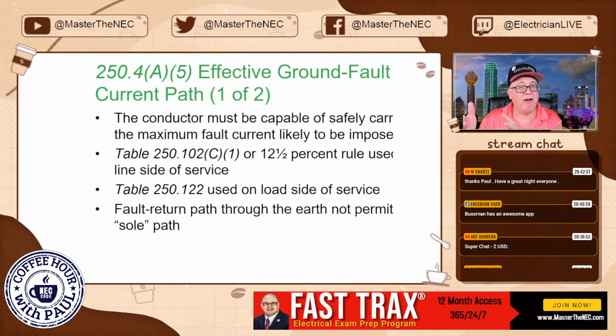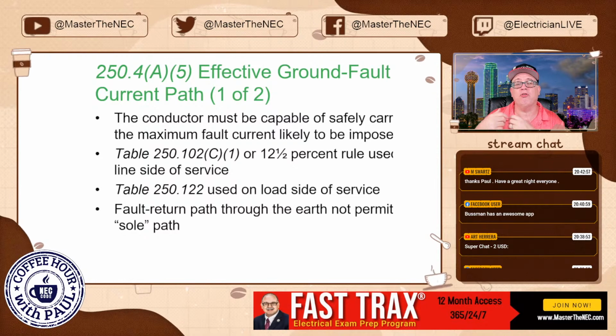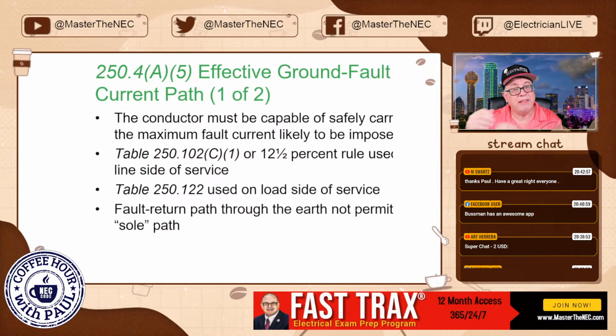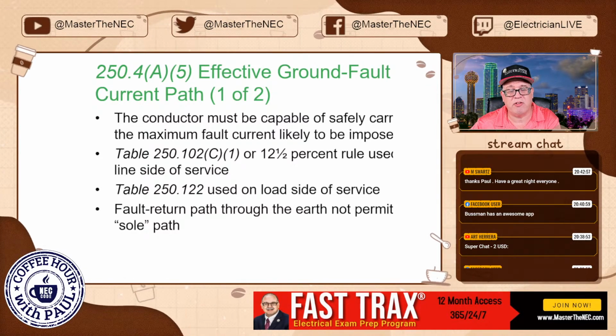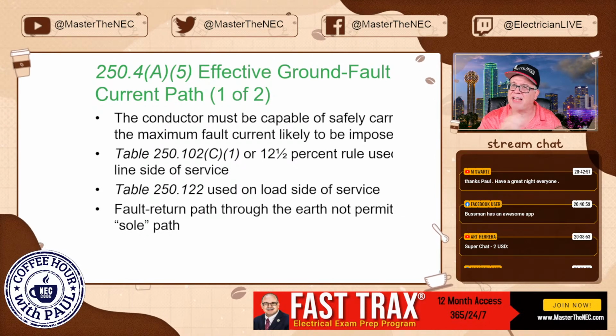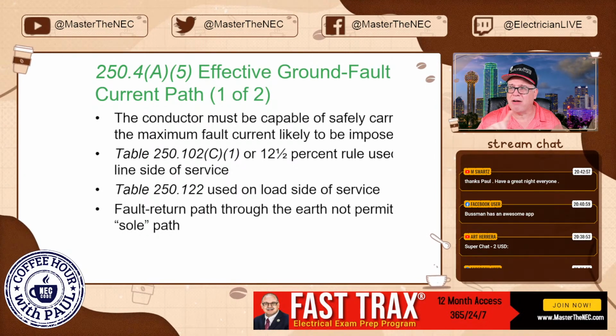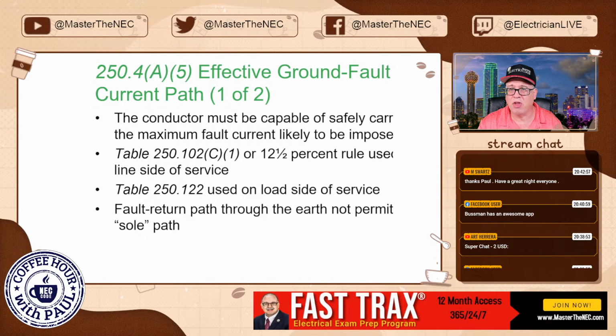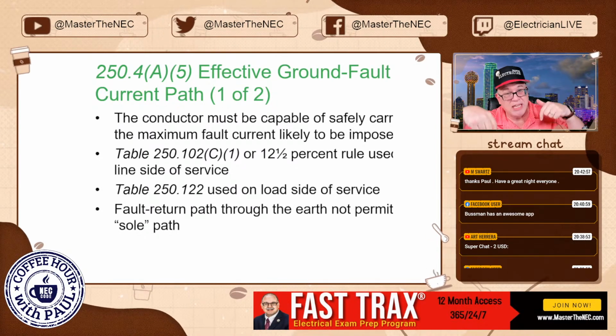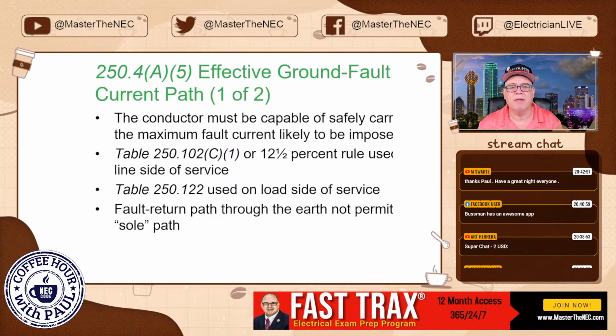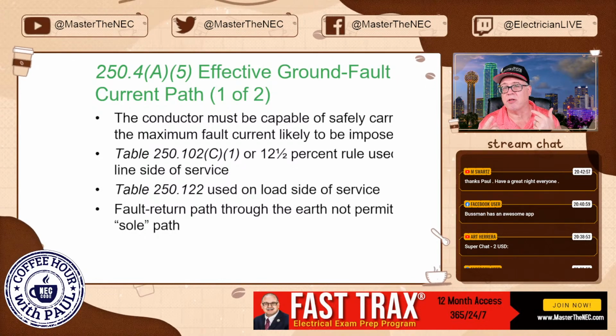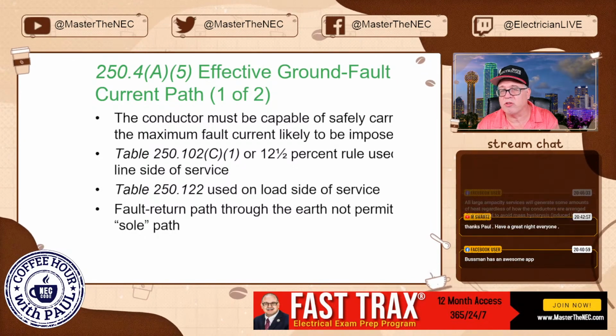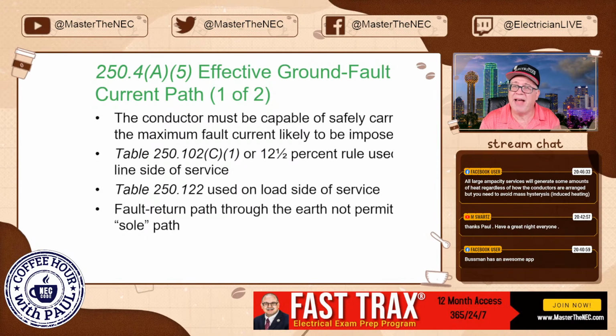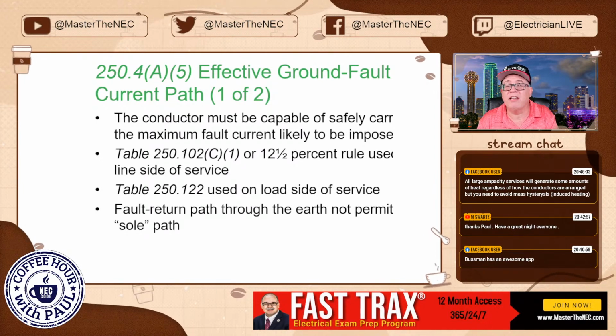But out there, I've got a feeder running to a remote distribution panel that is going to have a grounding electrode system. But I still have to have that connection with that equipment ground. I'm not going to go through the earth. Even though both of them have ground rods into the earth, absolutely not. Is there multiple paths? Absolutely. But the current is going to travel on the path that provides the lowest level of impedance.